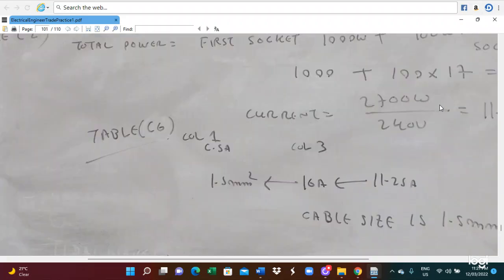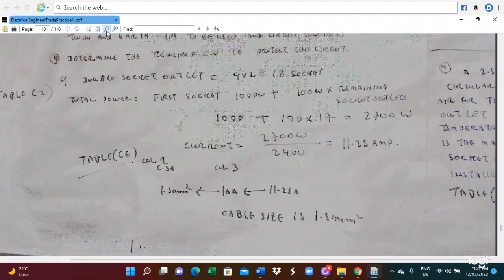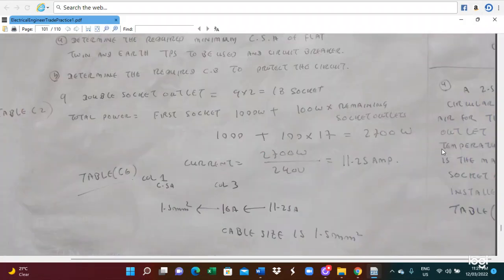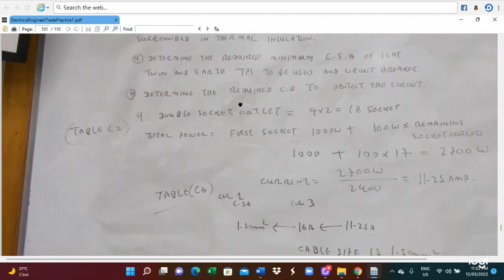Then we saw the sum problem. We have to determine the required circuit breaker to protect this circuit. In this case, there are 9 double socket outlets, so 9 multiplied by 2 gives 18 socket outlets. What is the power? The first socket outlet is 1000 watts, and each additional socket outlet is 100 watts multiplied by the remaining socket outlets. This is the rule, so we have to find table C2 of the AS3000.